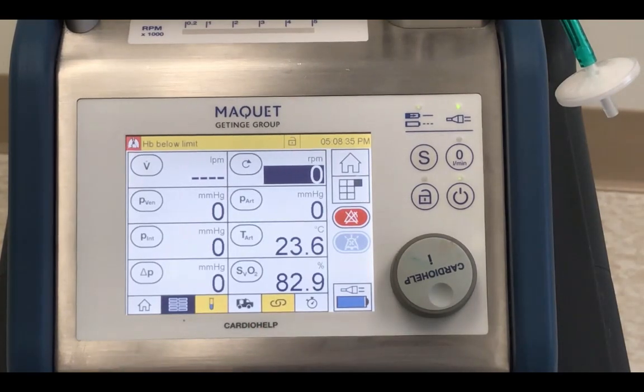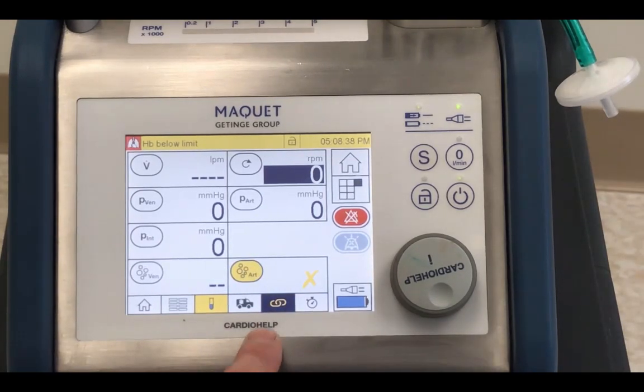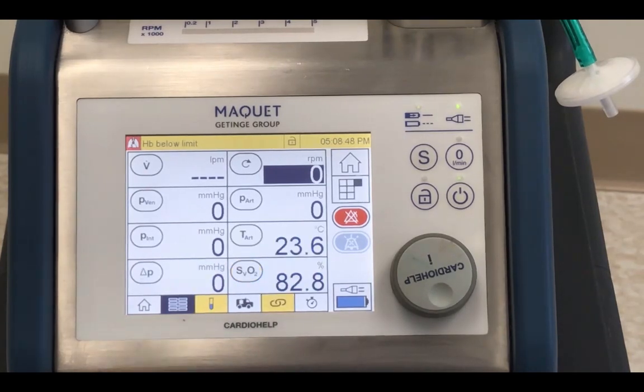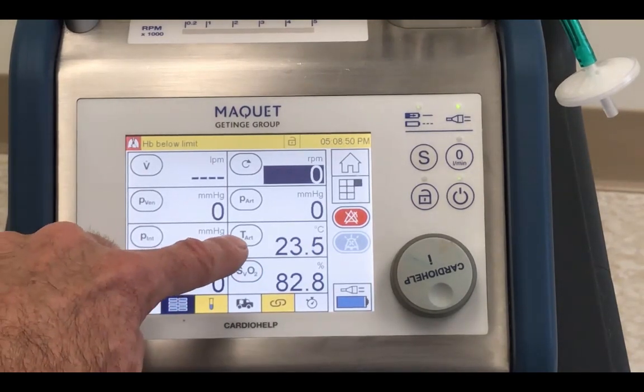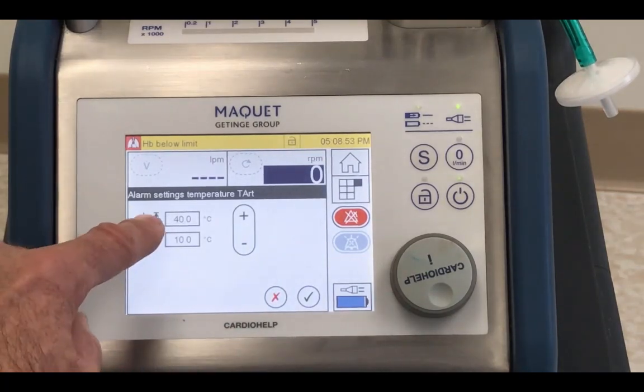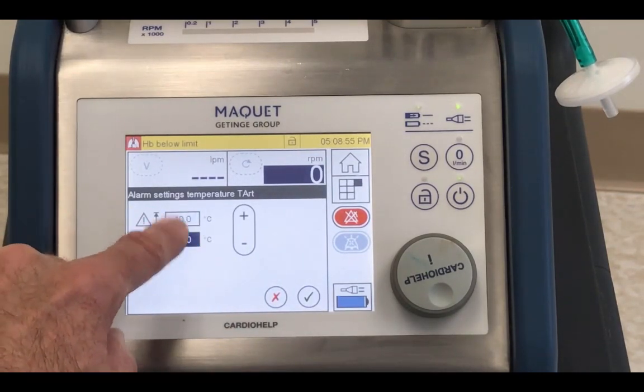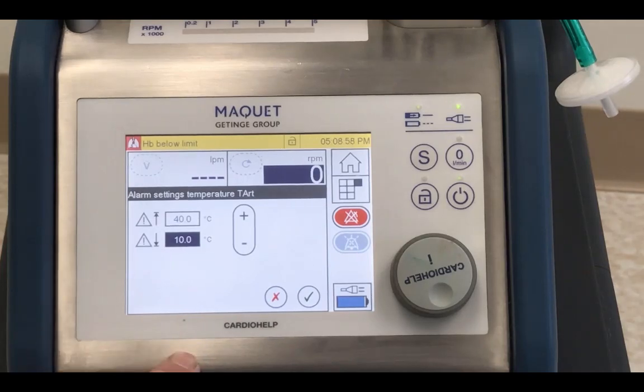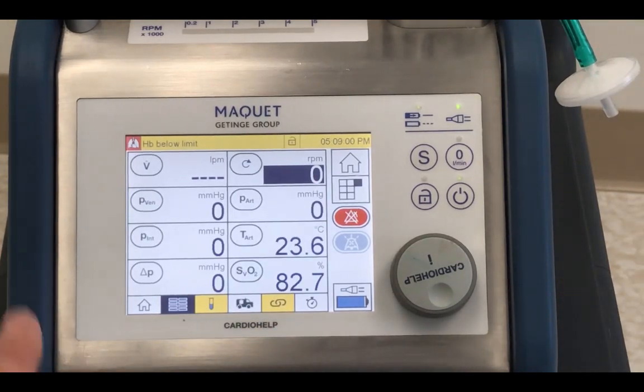You can set alarms. If we go to the intervention screen, you see there are no temperatures here. The pump won't take control of your system and turn RPMs up or down based on a temperature. But you can set limits around that. So you can go to your temperature arterial, and you can tell it when you would like to get a beep of some kind, if it's above this or if it's below that. Very smart system. You can tell it to monitor a number of items, and it'll let you know as soon as you leave your parameters. With that, I think we've covered everything that's on the screen.